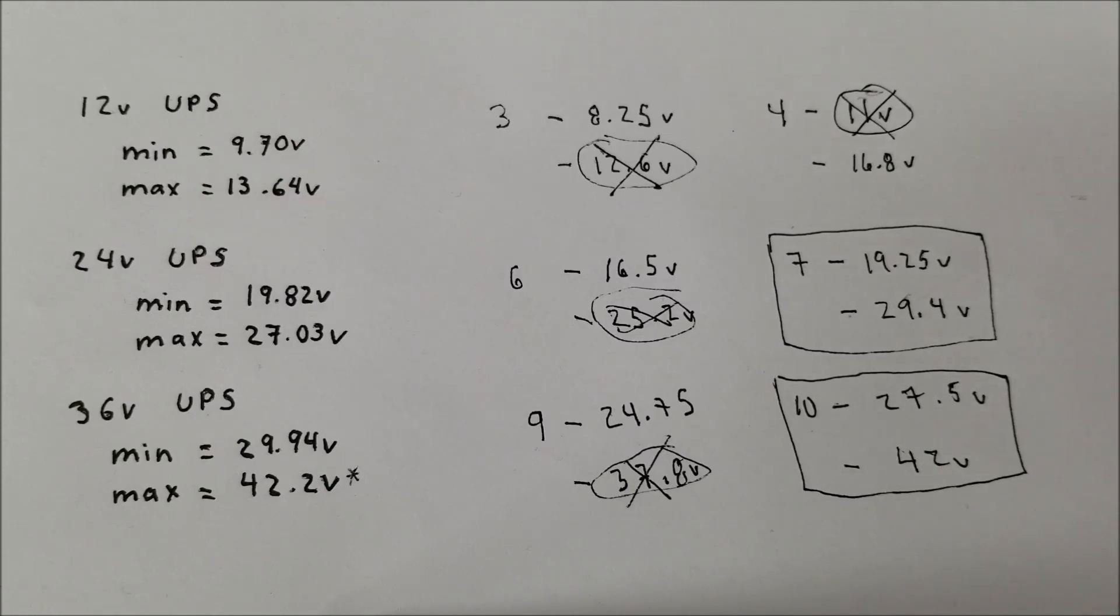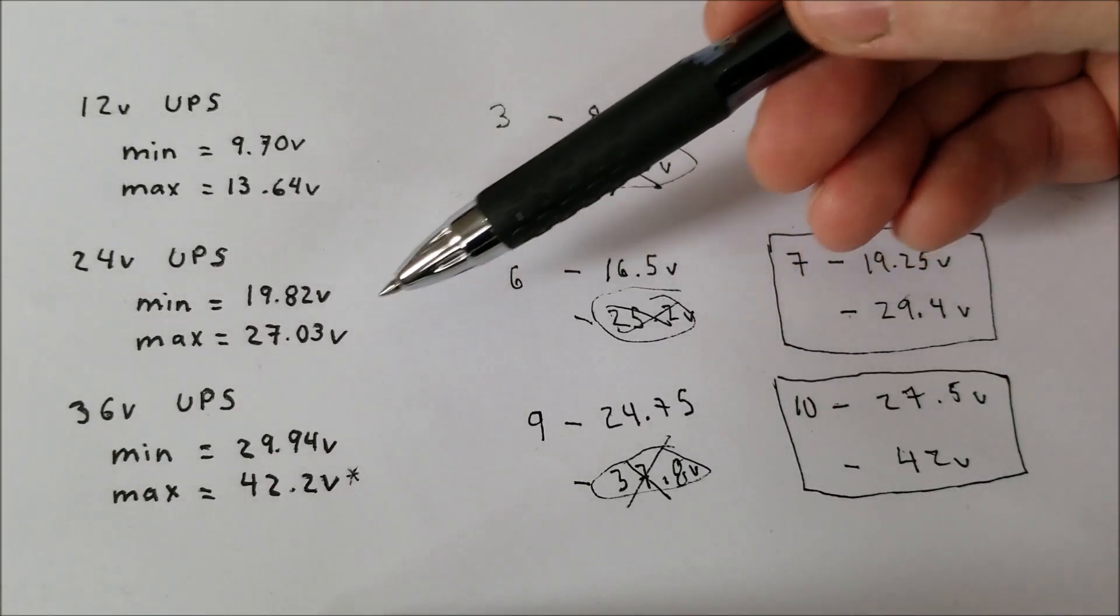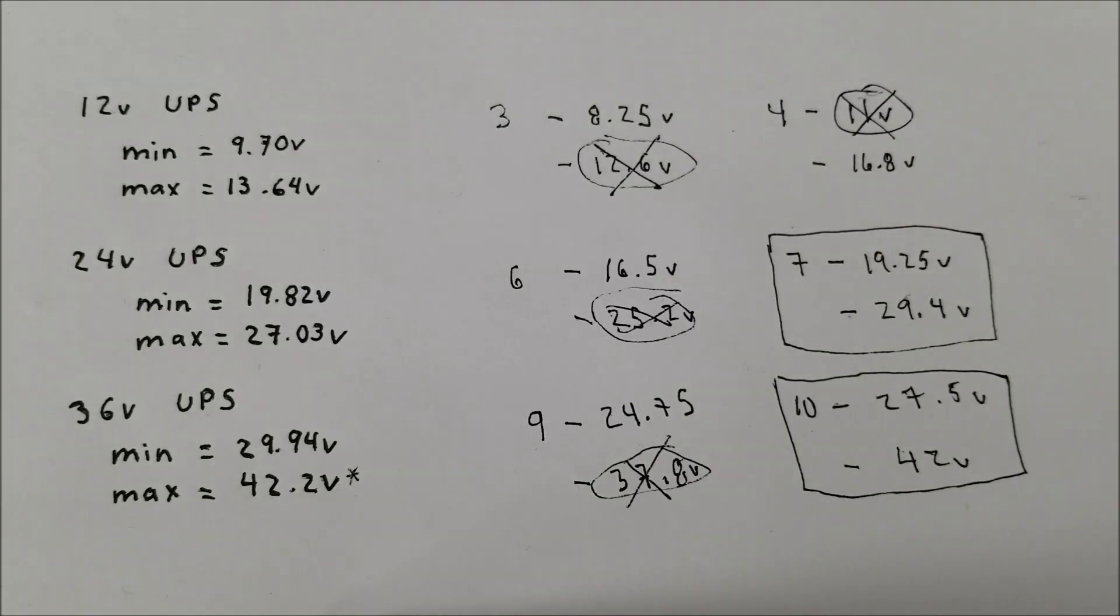Now one thing we have to note is that for this one here, the full charge voltage is obtained at 29.4V, however, the UPS will stop charging at 27V or a little above. Now what does that work out to? So 27.03V, we divide that by seven cells. That means each cell will only see 3.86V at the max. So that's quite far from being fully charged.